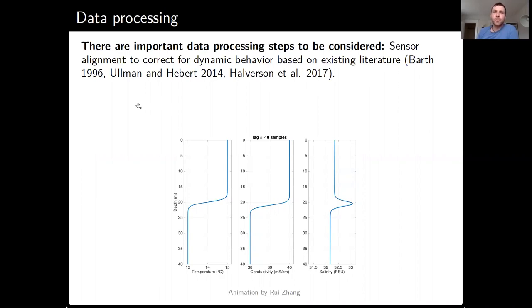One of the largest dynamic errors to consider is aligning temperature and conductivity properly. Those two measurements have different response times. The temperature actually takes longer to respond than the conductivity. Conductivity is an electric measurement, so it's for all intents and purposes instantaneous compared to temperature.